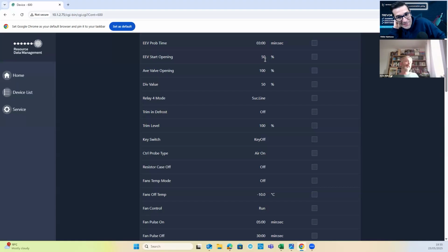Yeah, 100%. And it's another one where, let's say you've got a 12-foot frozen case that defrosts with electric heaters. Especially if it's got low speed fans when it's on defrost, if you set start opening to 10% and you're controlling on probes, the chances of you having any liquid arriving at that probe before the valve stalls is very slim. So you need a chunky start opening to get liquid to it. If you're operating a case that's chilled and is off cycle defrost, you can set that to like 10%, 20%, and it will get away.